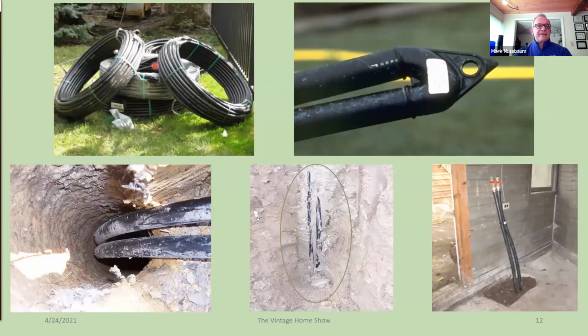Looking at the loops themselves, these come from the manufacturer. They're cut to the length that you're going to go. In the area I typically am drilling somewhere between 150 to 500 feet deep on the boreholes. When you have a small lot, you need a certain amount of pipe in the ground to handle the loads that you're going to see moving between the ground and the house, and you can either go with fewer boreholes, deeper, or more boreholes, shallower. It kind of depends on what your driller likes to do and how much ground you've got available to put it in. But these come pre-made.